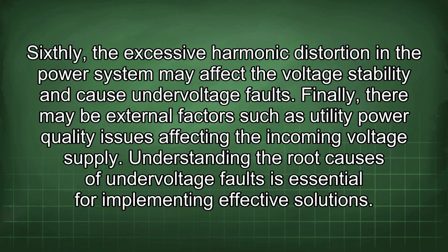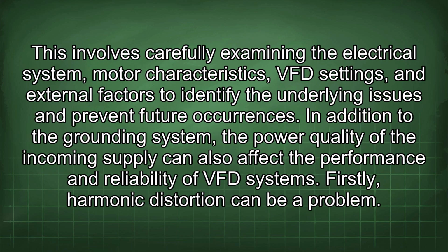Sixthly, the excessive harmonic distortion in the power system may affect the voltage stability and cause undervoltage faults. Finally, there may be external factors such as utility power quality issues affecting the incoming voltage supply. Understanding the root causes of undervoltage faults is essential for implementing effective solutions.